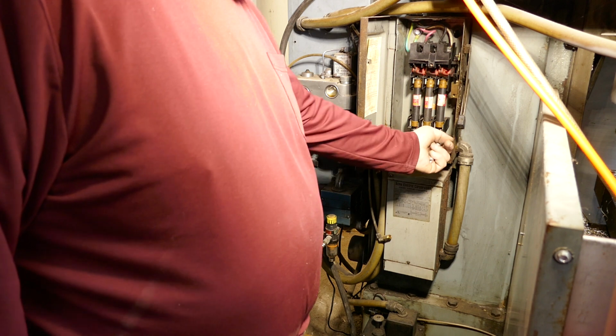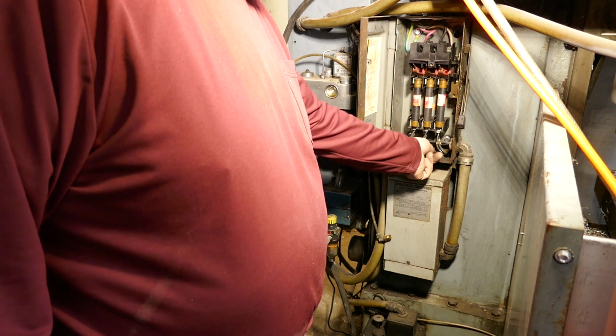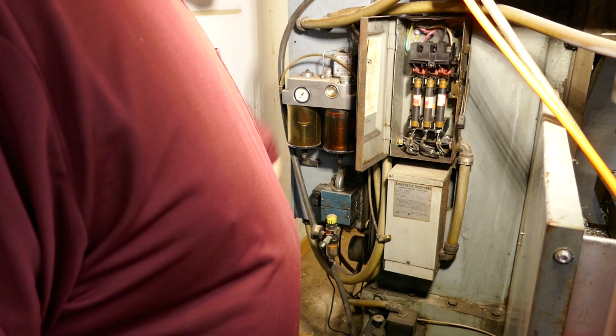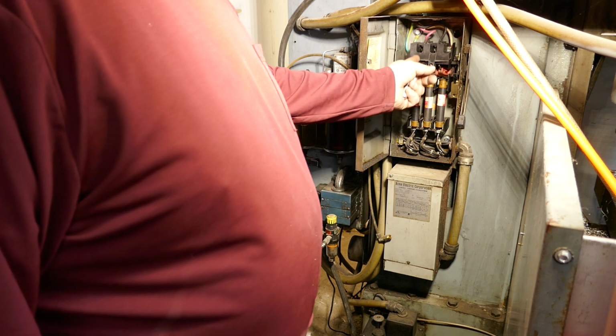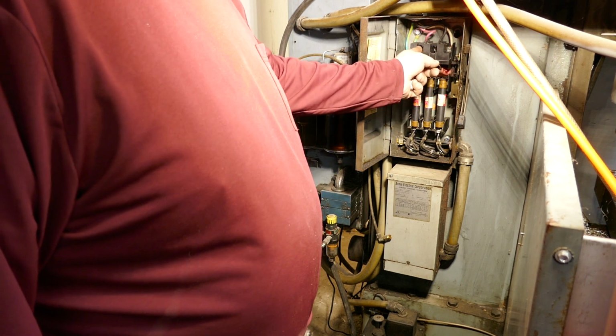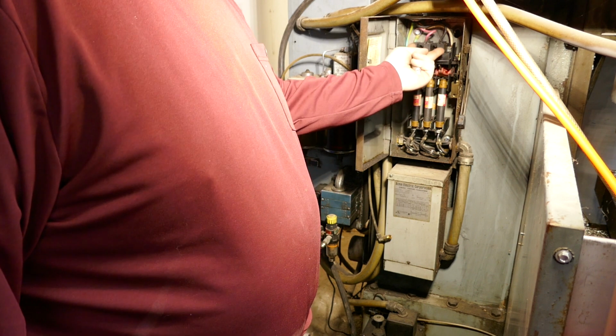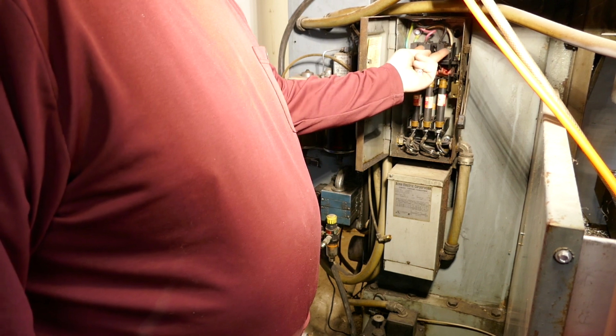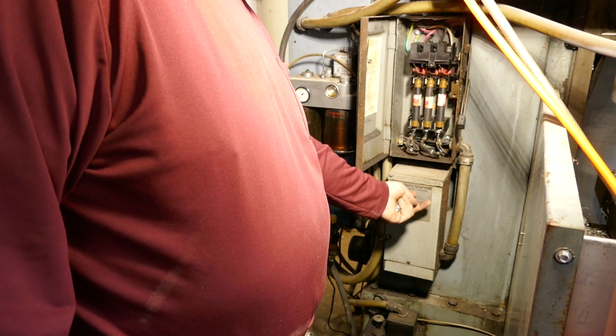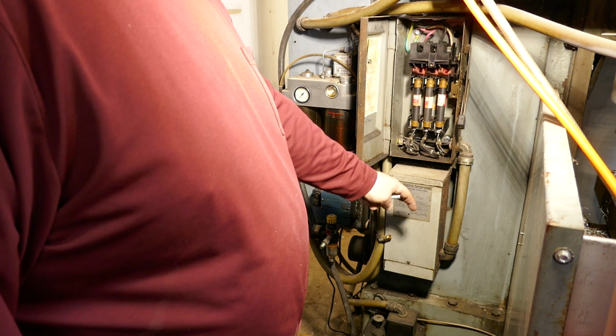Now phases 1 and 3 are connected to this transformer. So once I connect all this back up, I need to verify what my voltages are on the three phases, because I want the two utility phases to be going to this transformer down here, because this is what all the electronics run off of.